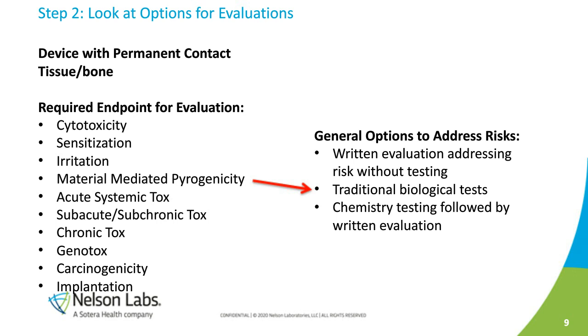For the systemic tests, like systemic toxicity, subacute, subchronic, chronic, and so on, right? There really are a lot of options in the way that you address this risk, and this comes to another point where we've seen and learned a lot over the last year. Depending on the device type, it may be possible to do a written evaluation for these endpoints without doing any type of testing. So sometimes you'll have a device type like an anodized titania piece, and this anodized titania piece has excellent evidence associated with it that it's totally clean. Based on that, we can say, okay, there are no surface residual chemicals on there that could possibly result in repeat and chronic exposures to any chemical that might cause any of these endpoints.